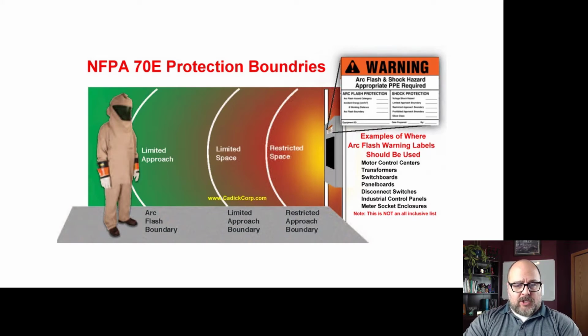So this is a demonstration of the boundaries. You have restricted space and limited approach, and the amount of PPE one would require to withstand an arc blast or arc flash is dictated by this. As you double the distance, it reduces the energy because it's expanding out—unless you're in a corridor where it can't expand out, then you're going to have to back up further. So it's about how the energy is released and dissipated over space.